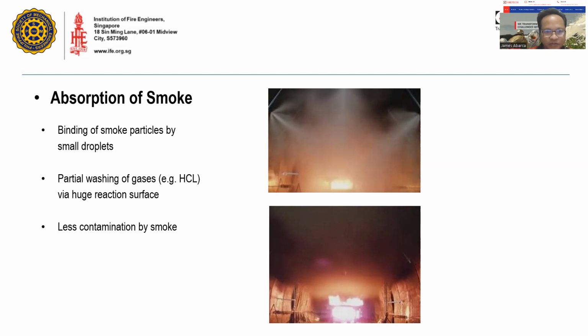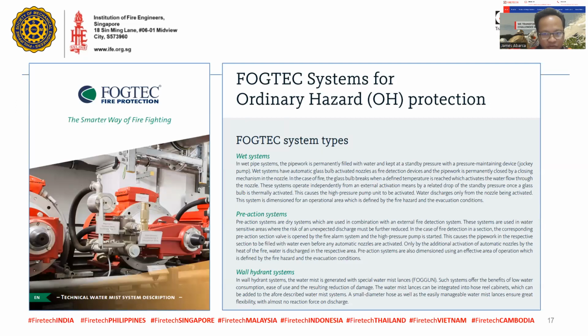Okay, so that's also one of the advantages. Now, if you're going to look at this chart, I mean, sorry, this figure, water mist can be applied to different types of systems. It can also be a wet system like the sprinkler system. There is a pump, there's piping, there's a discharge device, and there is a head that has to be broken by temperature. That glass bulb will open and the mist will go out.